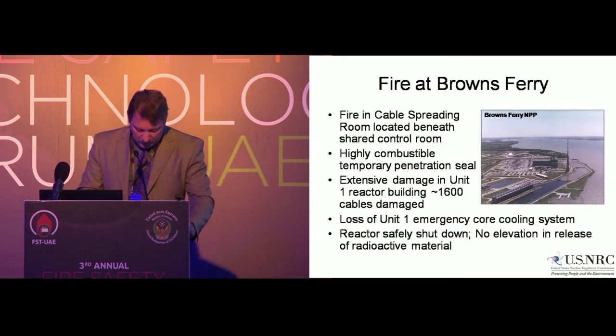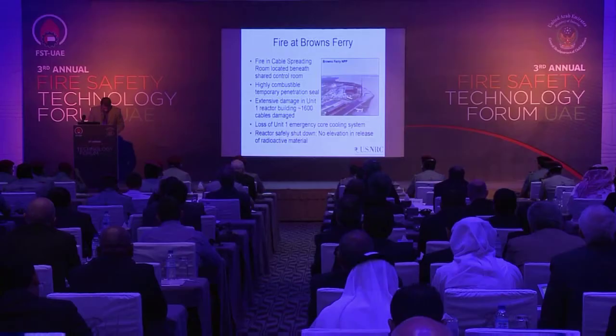At the time of the Browns Ferry fire, Unit 1 and Unit 2 of Browns Ferry were operating, and a third unit was under construction. Units 1 and 2 shared a common control room with a cable spreading room located beneath it. The fire started in the cable spreading room at a cable penetration through the wall between the cable spreading room and the reactor building for Unit 1. A slight differential pressure is maintained across the wall, with the higher pressure being on the cable spreading room side. The original penetration seal had been breached to install additional cables required by design modifications.